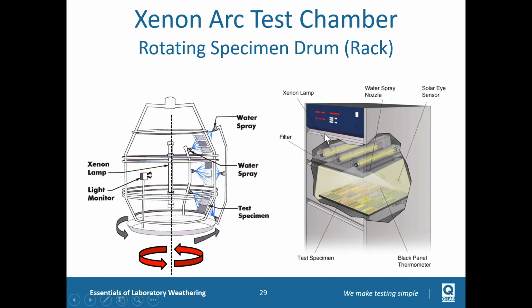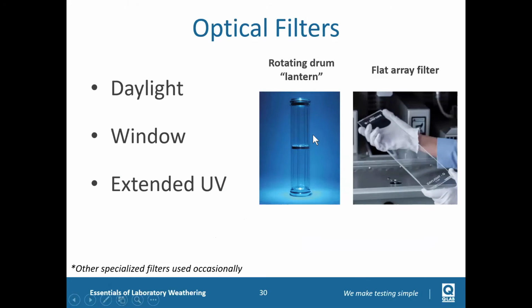Okay, so these are the different filters. This is a filter for XE2. I've told you that XE2, the QSUN XE2, is the rotating drum, not a flat array. So the filter needs to be a cylinder, like a lantern like this. The lamp will sit in the middle and the specimens will be around it. And for XE1 and XE3, we have our flat array filter. It's like a piece of glass, but it's special glass. We have our daylight, window, and extended UV families.